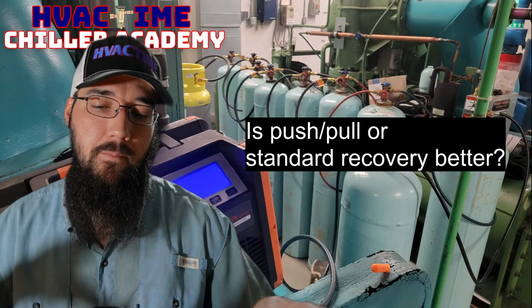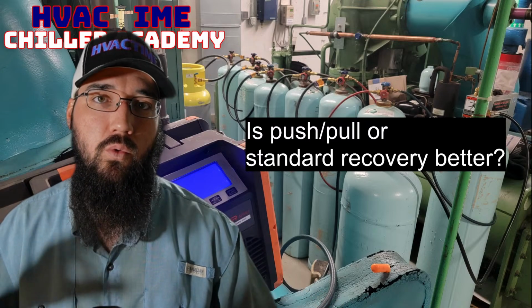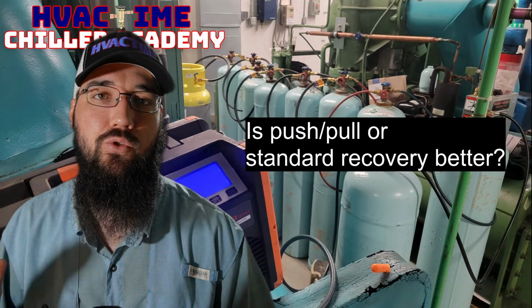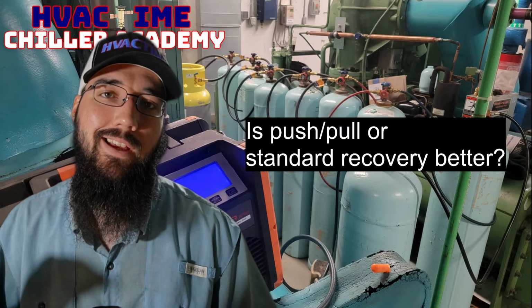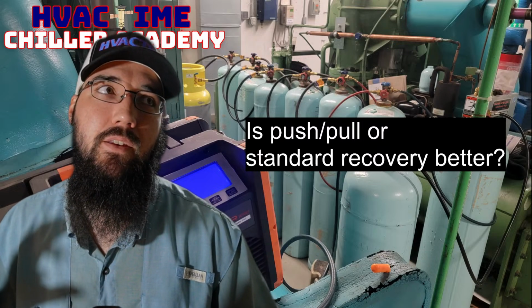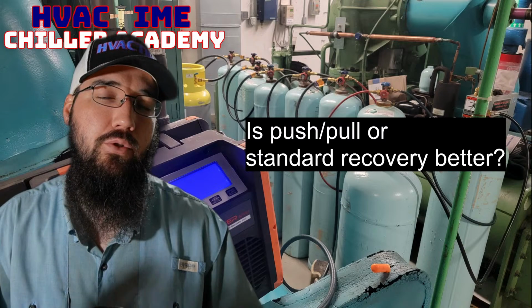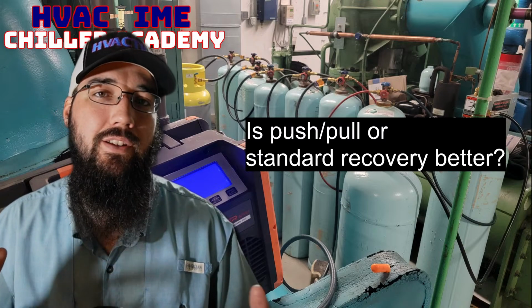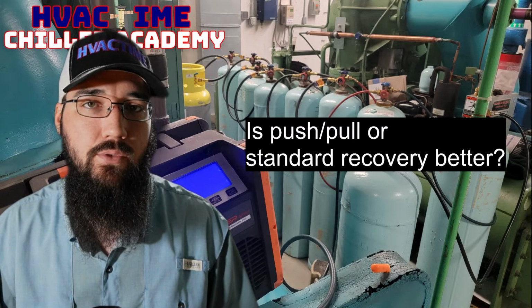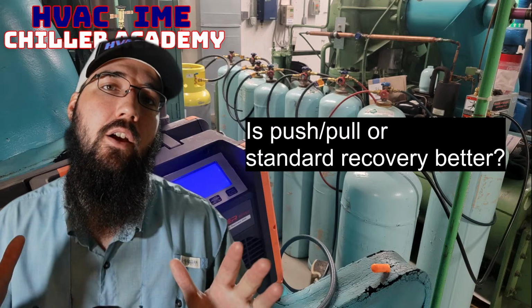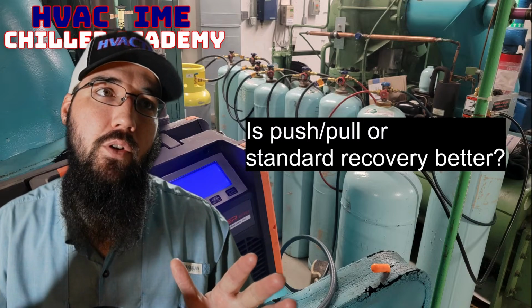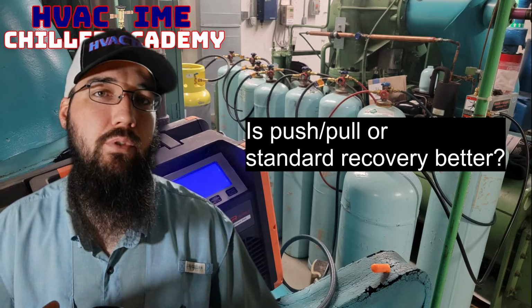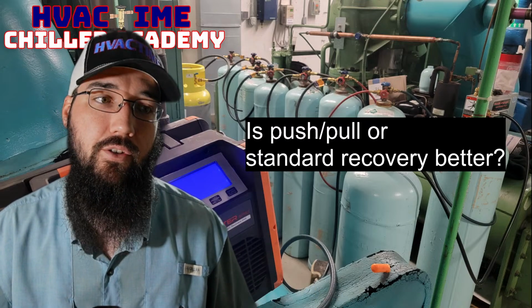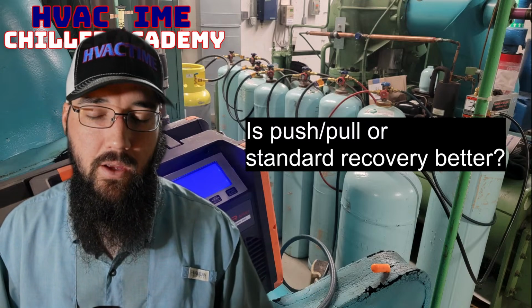So the objective of push-pull is to move the liquid refrigerant. One caveat is you still end up having to do a standard recovery process - the difference is you're only doing it on the vapor left in the chiller or the recovery cylinder, depending on your circumstances.